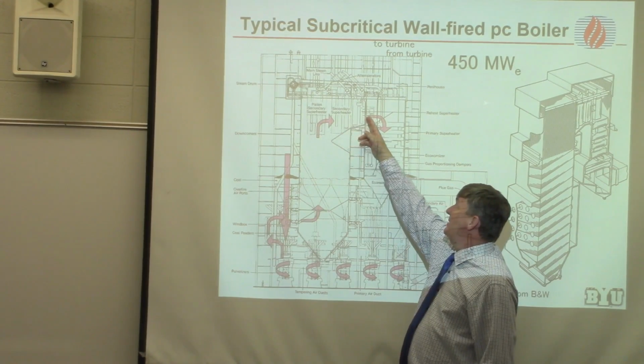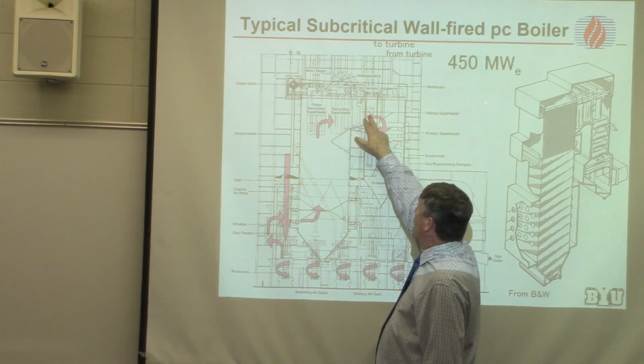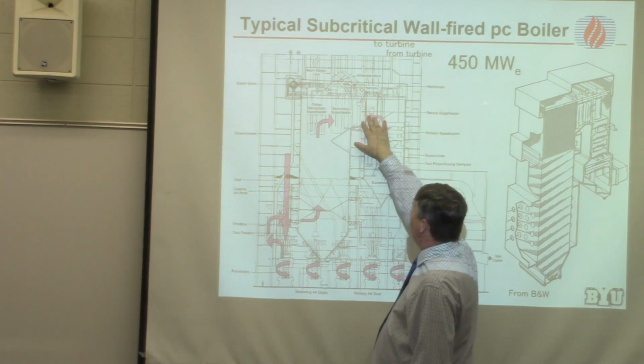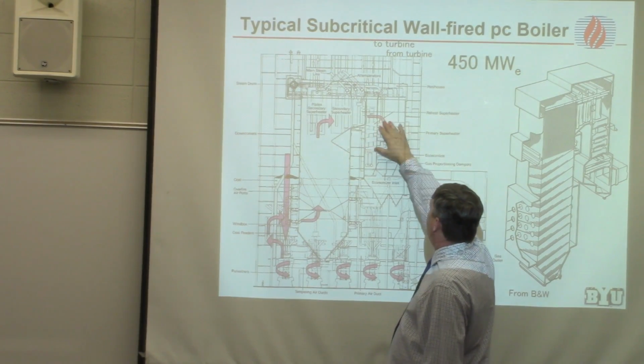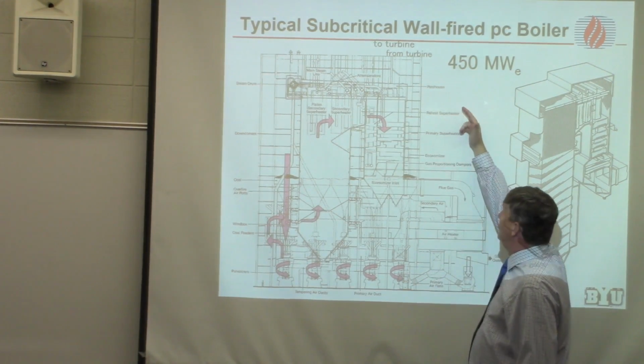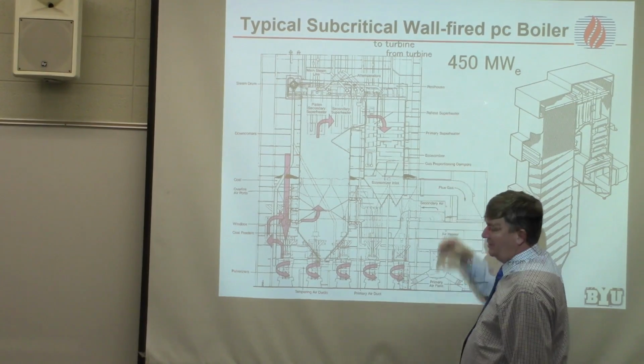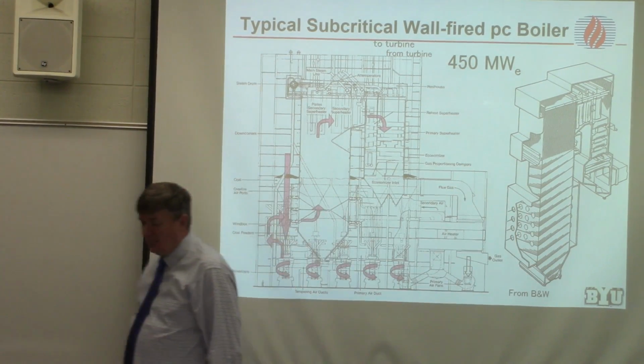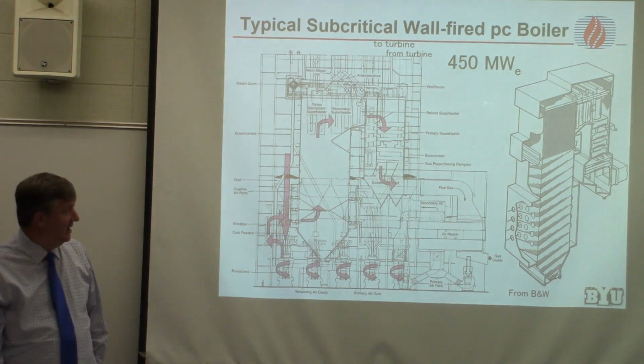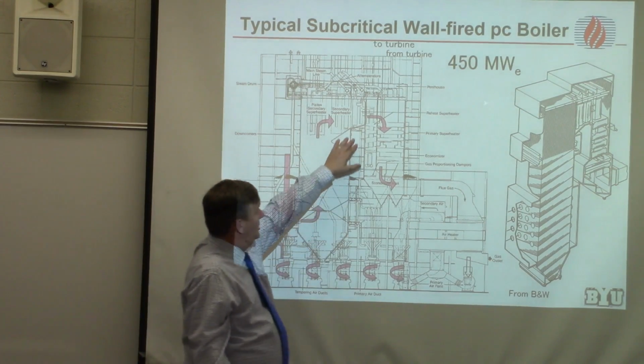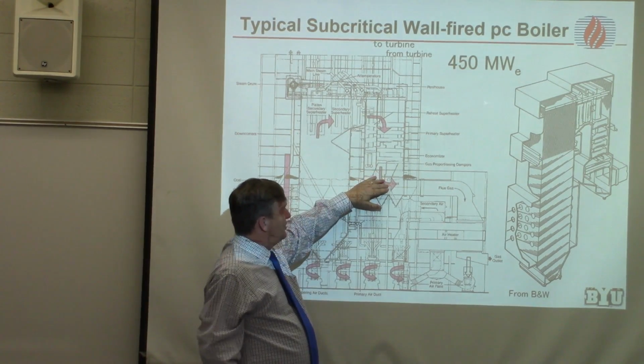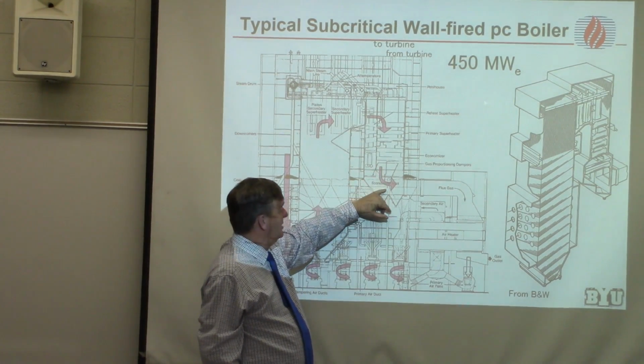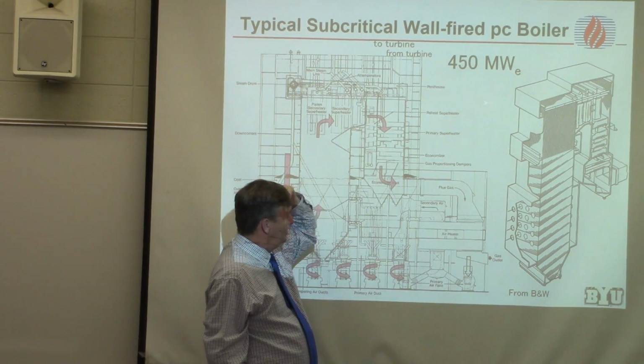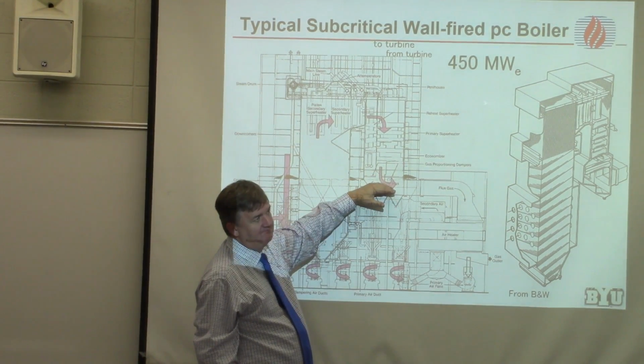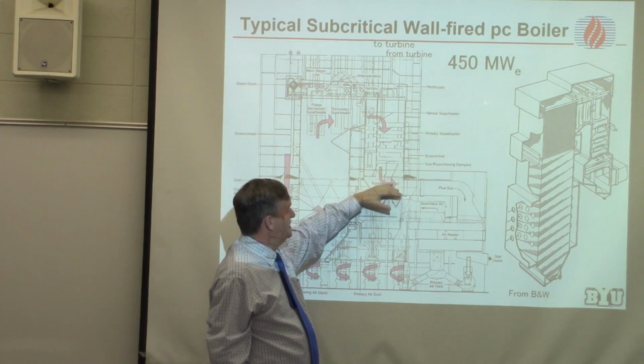So you superheat the steam as you come through here, and then the gas is cooling down, of course, as the heat is being absorbed. When you go down through here, you go through more superheaters and eventually an economizer, things that are heating up water now instead of steam. And the coal particles, these are just fly ash particles now, are just cooling down. By the time they get to here, they're down to maybe 200 or 300 degrees C.